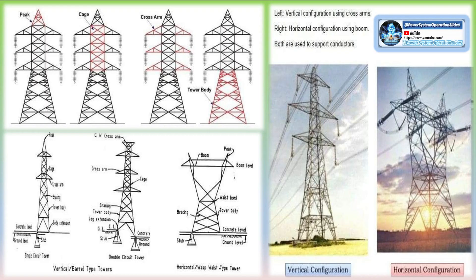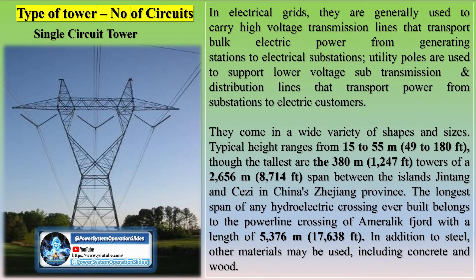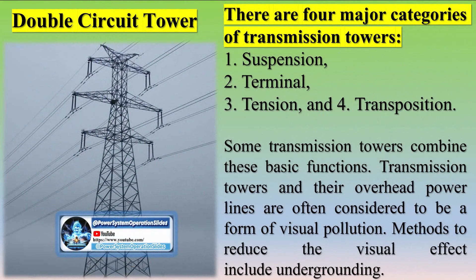Unlike suspension towers, tension towers use strain insulators to resist axial loading placed on the tower from the conductor's net tension. Dead-end or anchor towers support the weight of the connecting conductors and cater for the tension in the conductors, also using strain insulators. Dead-end towers are typically used at the end of a transmission line before the line passes to a substation or underground line. They are often installed periodically between a series of suspension towers to reduce the likelihood of cascade failure when a conductor on the transmission line fails.